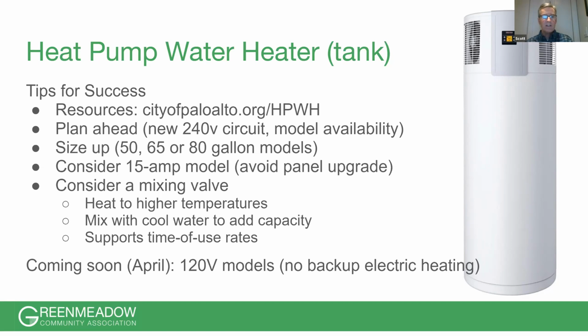For sizing, you'll often want to upsize slightly from your existing water heater, typically by 5 to 10 gallons. So a 40-gallon tank might go up to a 50. They also have a 65, but often a 75-gallon might go to an 80-gallon, because they have a longer recovery time. People want to make sure they have enough capacity.